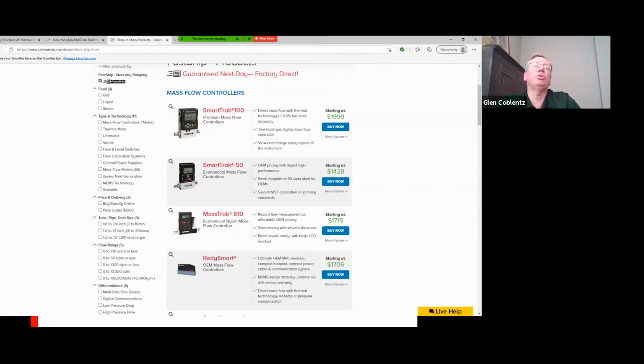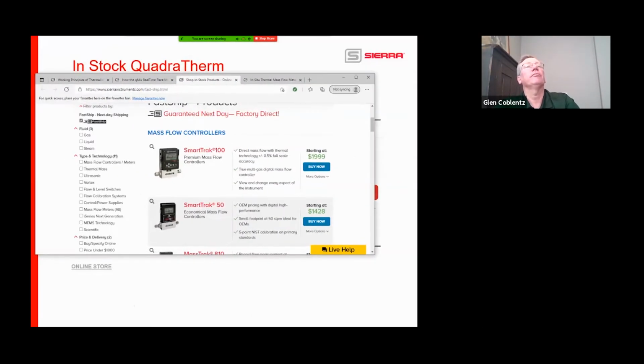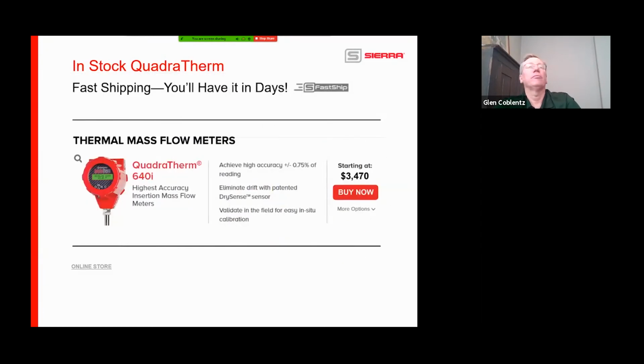But remember, these are all pre-calibrated. So some of these are going to be inflexible, like a 100. If it's 10 standard liters per minute, it's 10 standard liters per minute. But if the customer wants to measure 7, well, guess what? It still works. They just have a little bit more on the high side there.